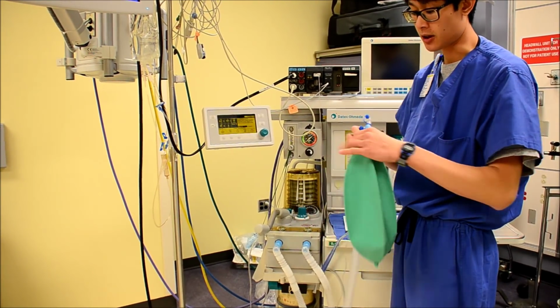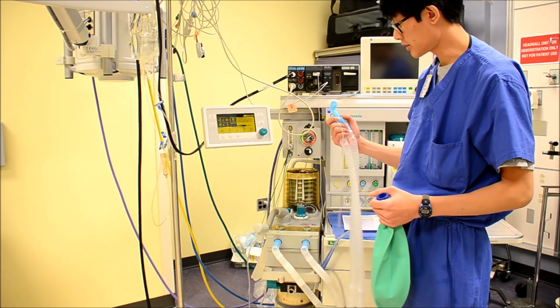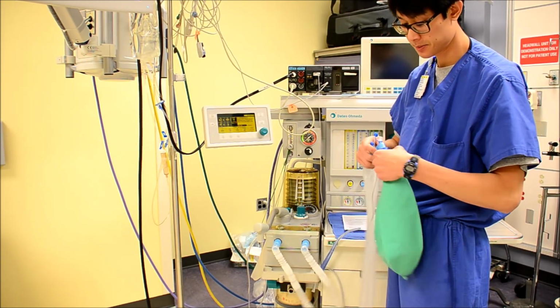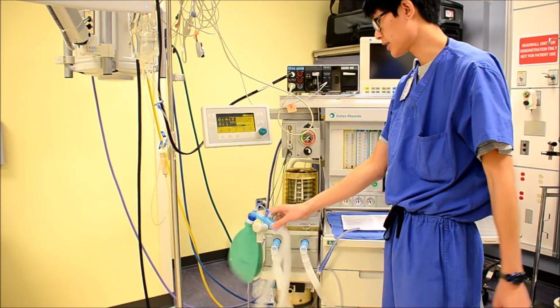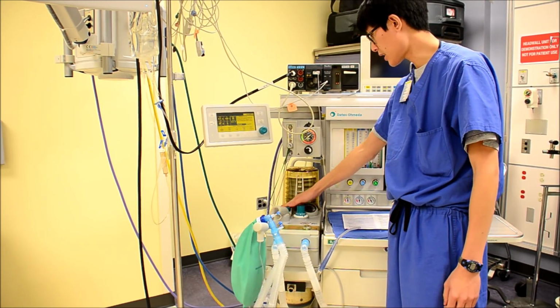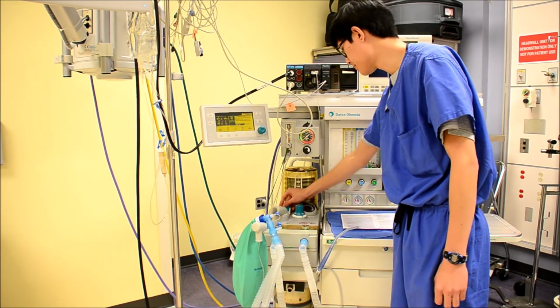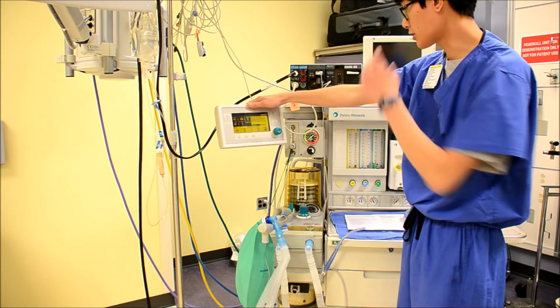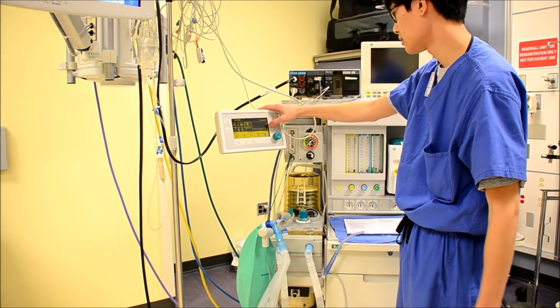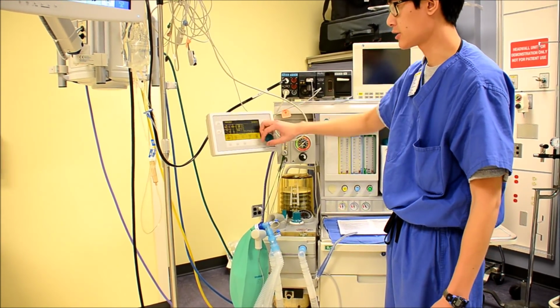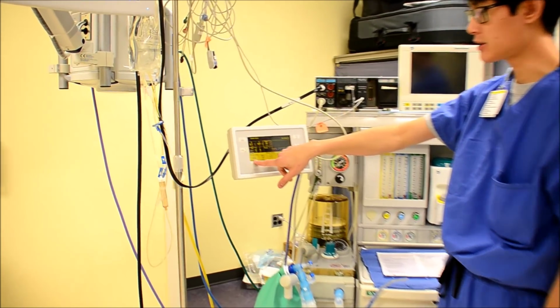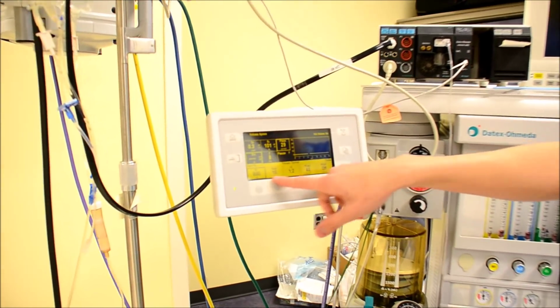So you're going to make an artificial lung, and you do that by connecting your circuit to your bag. You can let that hang, and switch from bag mode to ventilator mode. And a quick way you can get this started is to change your vent setting. So it's already default set at 600 tidal volume and a rate of 10.